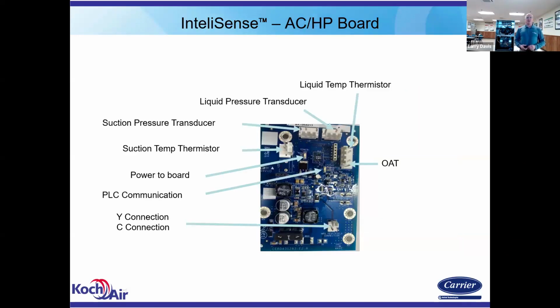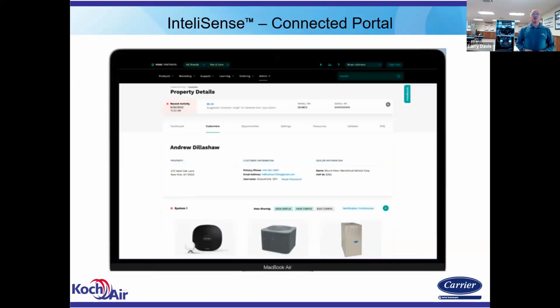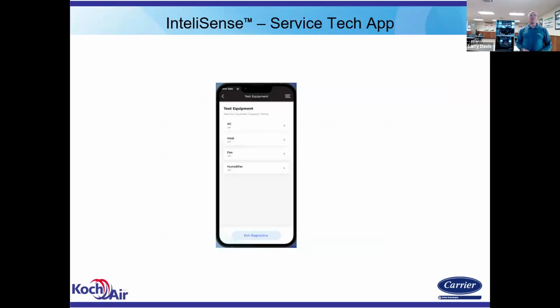This is the InteliSense board that's in the outdoor unit. We have a Y and a C communication that comes from our contactor. We have power to the power on an LED says the board's powered up. Comm light saying it's communicating, and they're your terminals for your transducers and temperature sensors. And then when you have it pulled up either on the portal or on your service app, you'll get that information. Okay. And that, again, gives you a little leg up before you go to the job.